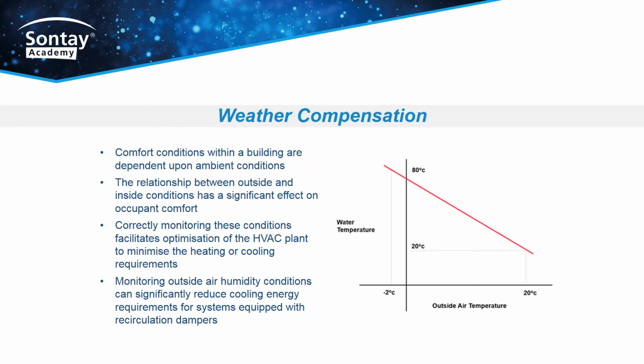Weather compensation. Comfort conditions within a building are dependent upon ambient conditions. The relationship between outside and inside conditions has significant effect on occupant comfort. Correctly monitoring these conditions facilitates optimization of the HVAC plant to minimize the heating or cooling requirements. Monitoring outside air humidity conditions can significantly reduce cooling energy requirements for systems equipped with recirculation dampers.